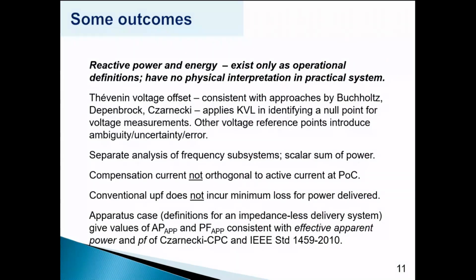Finally, we can define an apparatus case, which is the assumption of an ideal source at the point of connection, which allows us to compare with all other power theories. And what do we find? It gives the same values for apparent power at the apparatus and the power factor at the apparatus, consistent with effective apparent power and effective power factor as defined in the IEEE standard 1459 of 2010 and as used by Czarnecki. So we're not a million miles out, but by adopting this new paradigm of looking at things in the context of the delivery system, we come up with very different values.